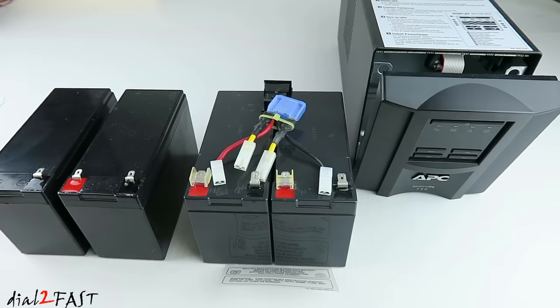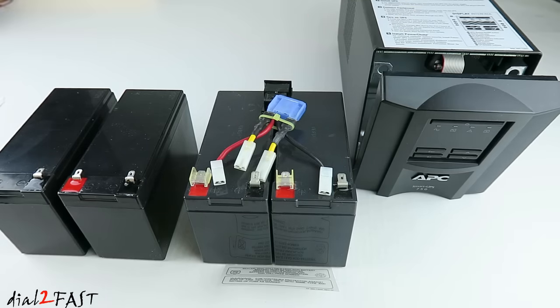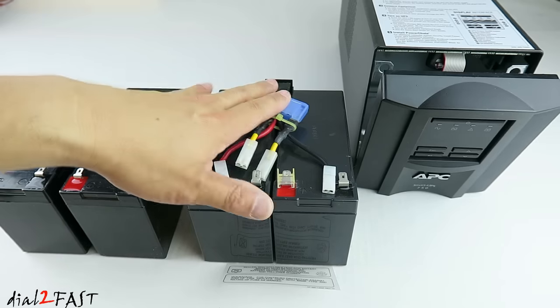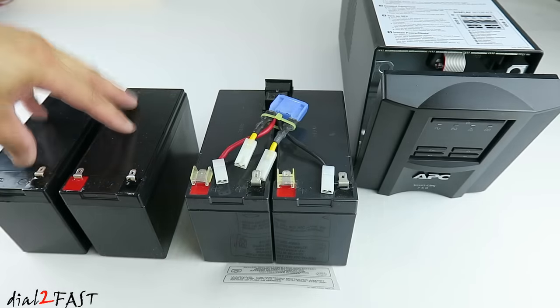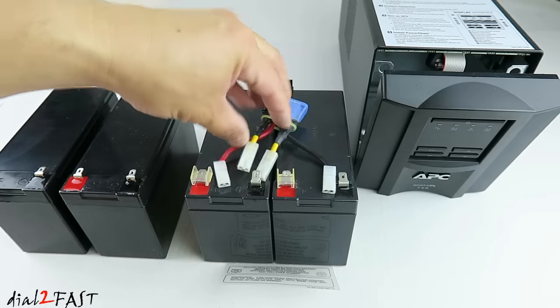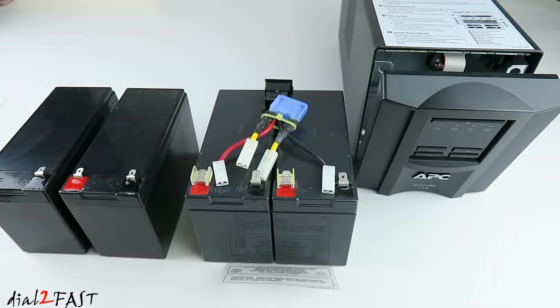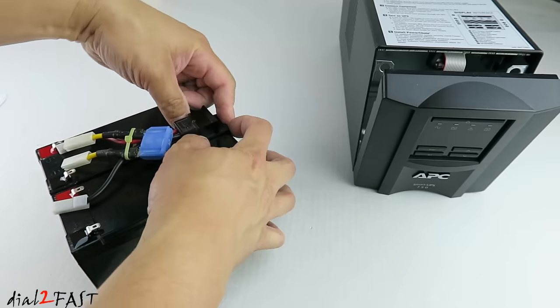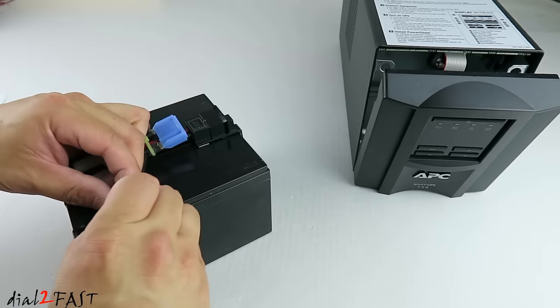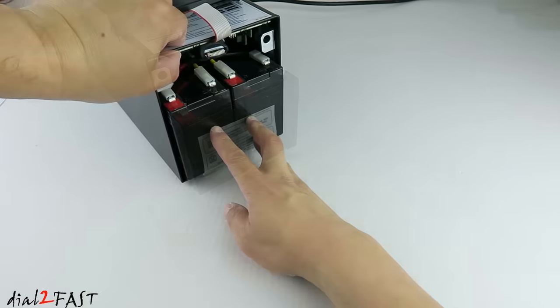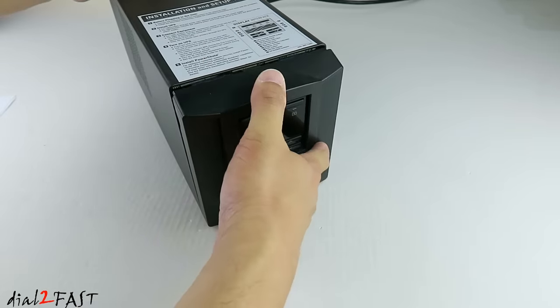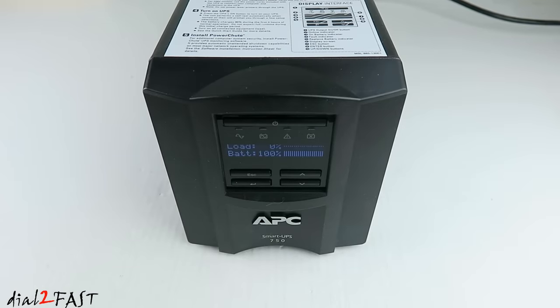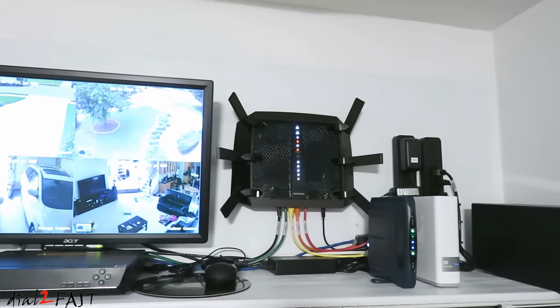One very important component that I'll be installing as part of the new setup is a good UPS. Over here is the APC Smart UPS 750. Now I've had this for a couple of years, but recently the internal battery lost its ability to hold its charge. And that's typical after 3, 4, 5 years of use. And this pair of batteries you see here were actually pulled out of the unit. And I got the new batteries on the left side here. This is the same rating and dimension as the original one. So all I'm going to do is transfer this wiring harness over to the new batteries and then install it back into the unit. And then it'll be up and running again. Let's turn it on.